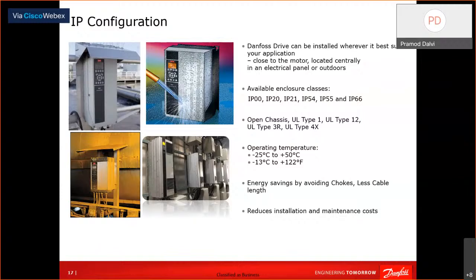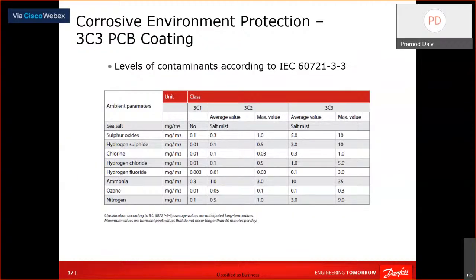Coming back to the reliability part, the IP protection is where we have invested, up to IP54 and 55, with high ratings up to 1 megawatt. We have IP54 drives. On the operating temperature, our drives are designed for 50 degrees. Definitely it saves cost, because the chokes are built in, so no additional AC chokes are required. This is the unique feature of Danfoss drives, which were launched in 2004 or 5.